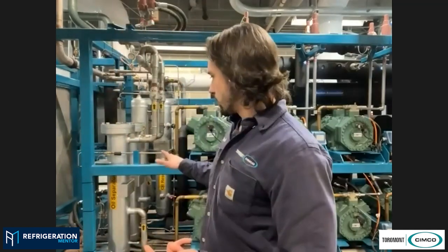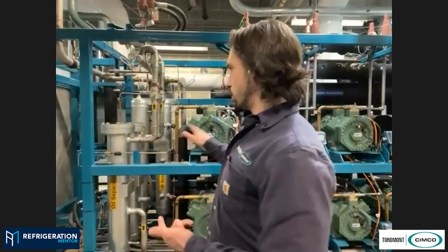I will say we did have an issue on startup where they had ice in and couldn't run a couple of the compressors, and having the two separate oil separators was a blessing because we could keep the package running but at a reduced capacity, as opposed to shutting the entire thing down. Usually that's what a lot of manufacturers do, so you can even do maintenance while it's still running if needed.